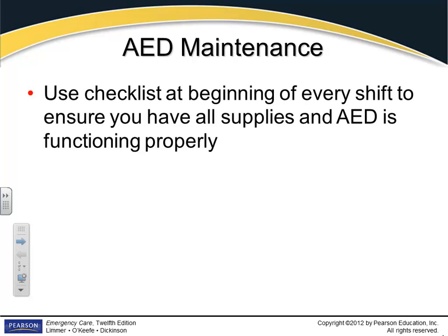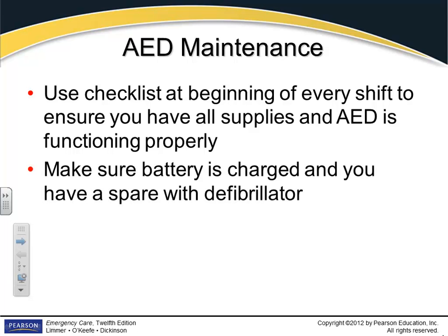Your AED should be checked every day. Check the batteries. Make sure it's functioning. It'll have a test button that you can push, and it'll run an internal test and print a report for you. But if it's not working, you're not going to be shocking anybody. The most common cause of AED malfunction is operator error, in that you have failed to check the batteries. Most commonly, that's the problem.